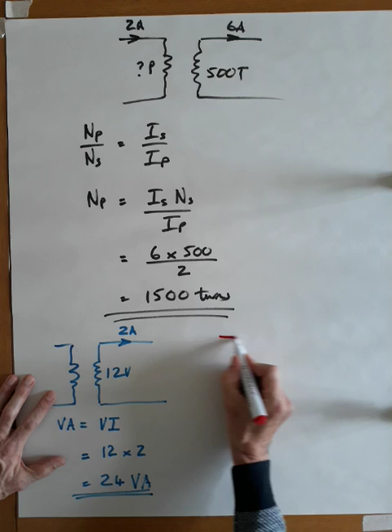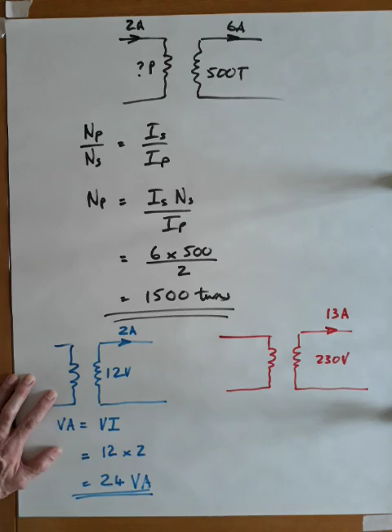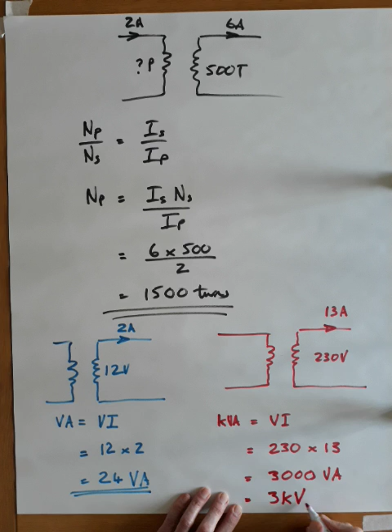Let's do a different example. Say we've got a 230 volt output voltage delivering 13 amps. What is the KVA rating of this transformer? KVA is voltage times current - put the numbers in: 230 times 13. I don't know the exact number, it's a fraction under 3000, but I'll call it 3000 volt amperes, or alternatively 3 kVA.